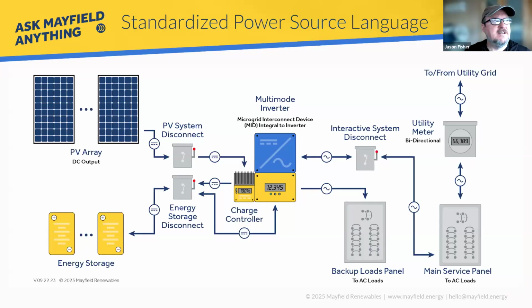Then from there, is this inverter part of this energy storage system or is it separate? You go back to what 706 says: it's for a listed energy storage system that may or may not include an inverter. If you provide documentation showing this is all covered under one listing, that should give you everything you need to argue that everything downstream is all part of the ESS and part of the listing.